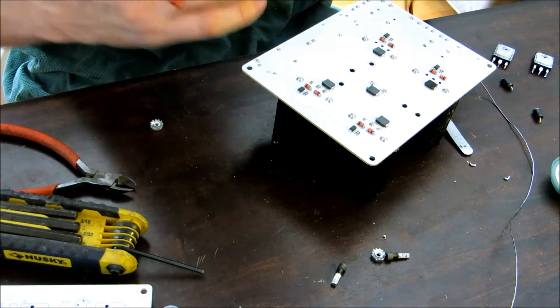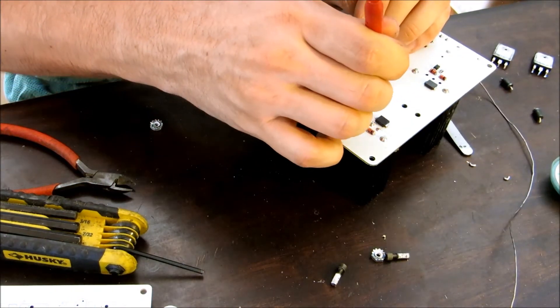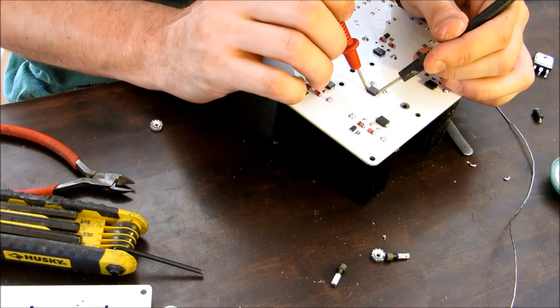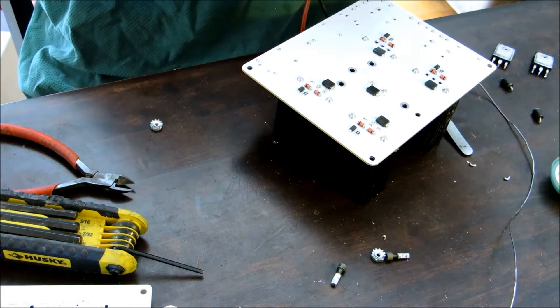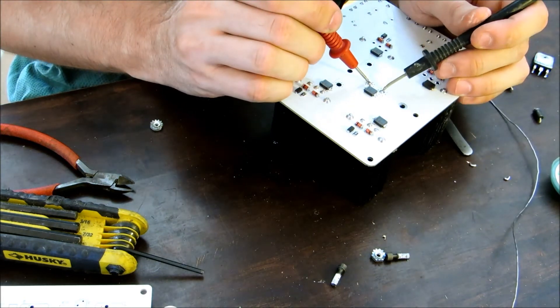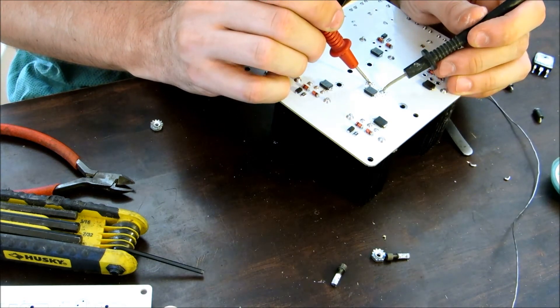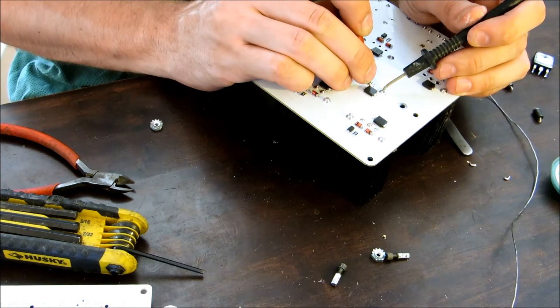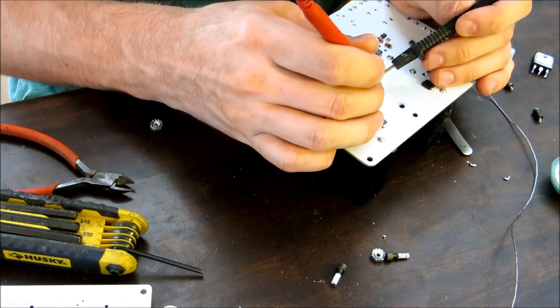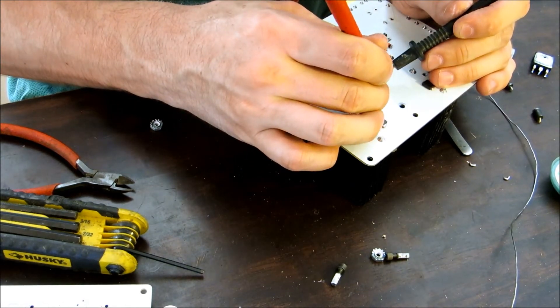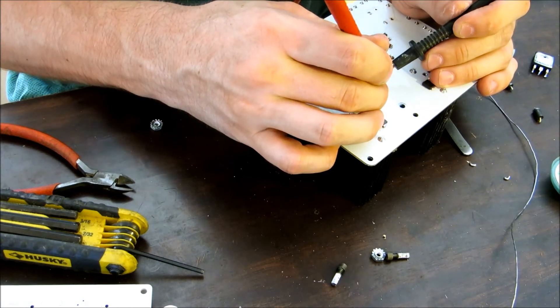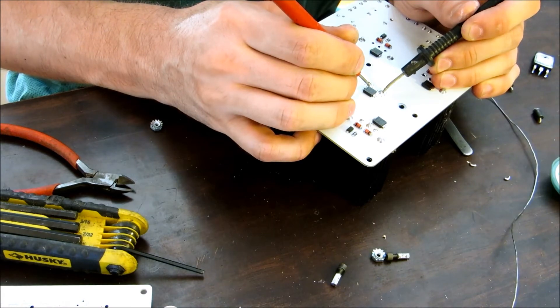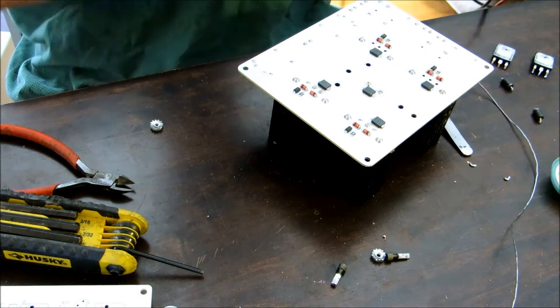I'm going to touch these up just to make sure they're all on there. So, let's get this middle one. You can also put this on continuity again and check the cap. Should be a short for a little bit of time. And then it discharges and then you get your open. That's how it should work like that. So, that looks good.